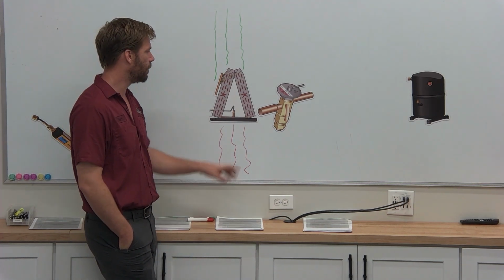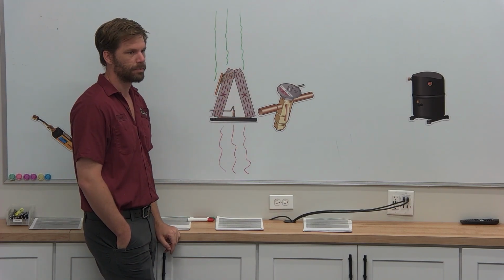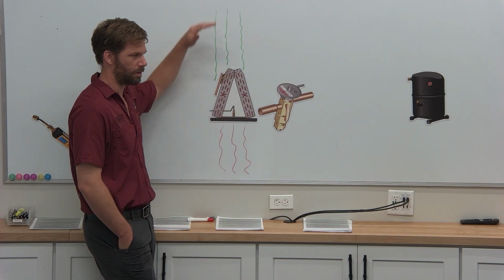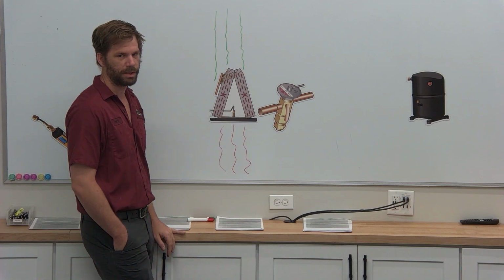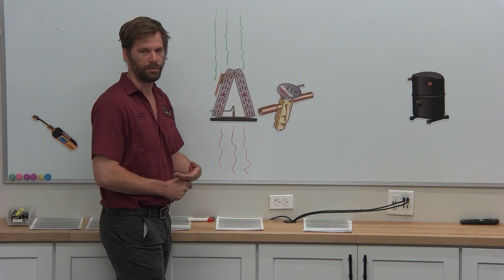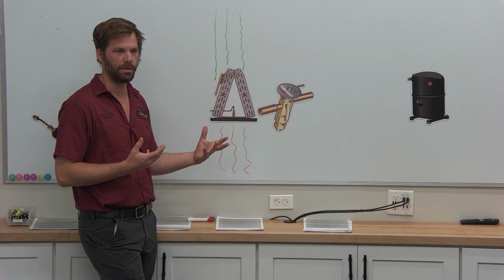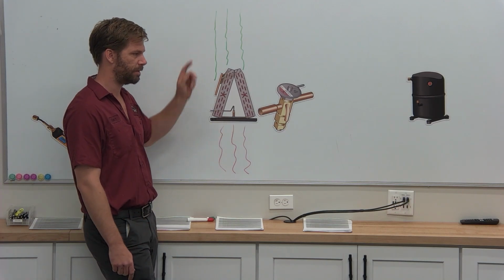And when you have a warm coil, what's that going to do to our temperature split? It's going to lower the split. We're not going to have as much heat transfer across that. Does that make sense? So when we're diagnosing something difficult like a TXV, and we're taking all of our different measurements to look for clues that we're getting it right, one of those key measurements is our temperature split.